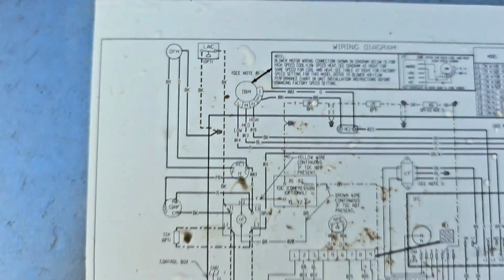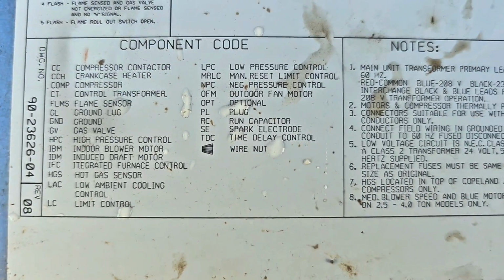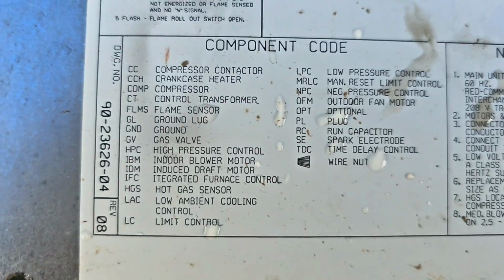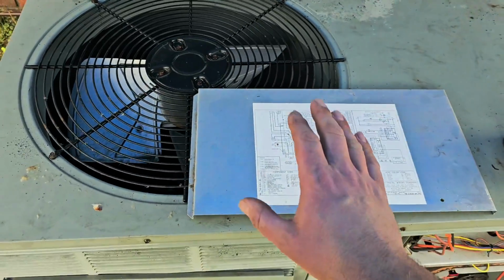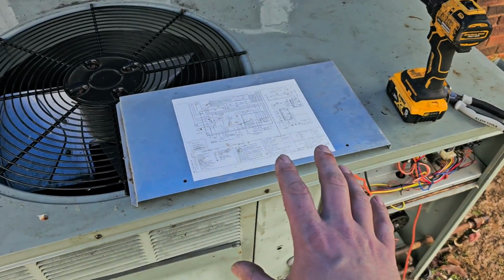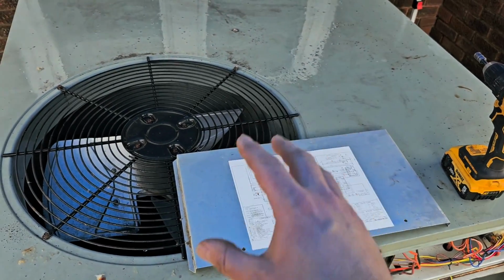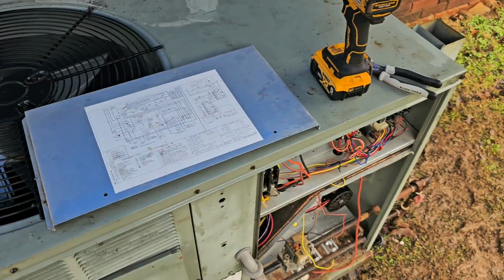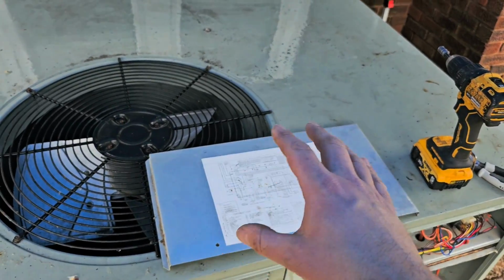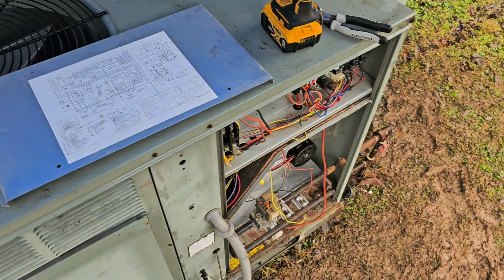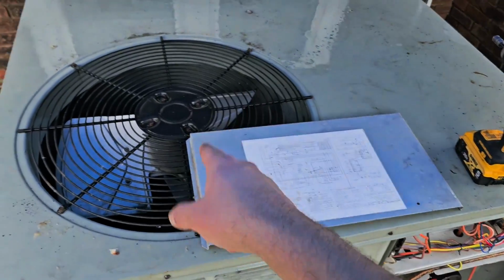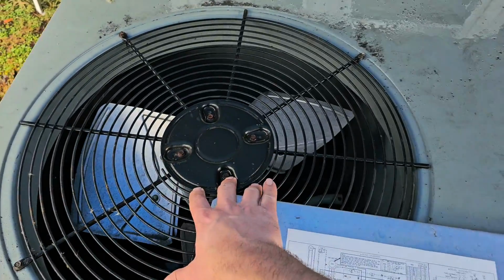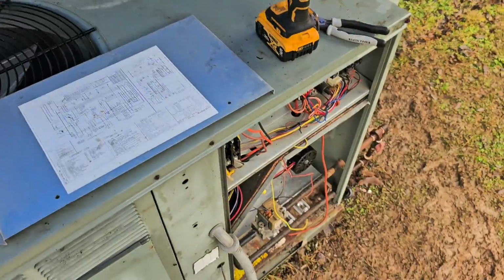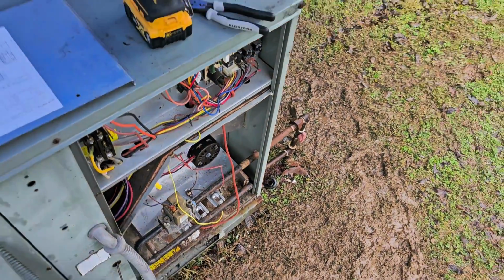So what is LAC? LAC should be down here, and it'll tell you what it is. It's a low ambient cooling control. So that's if you're running this package unit for cooling, maybe like a server room, computer room, data room, and it needs to run when you have colder outdoor temperatures, right? Low ambient conditions. And that'll basically allow you to cycle the outdoor fan and keep the head pressure up. Looks like the thermostat just satisfied.